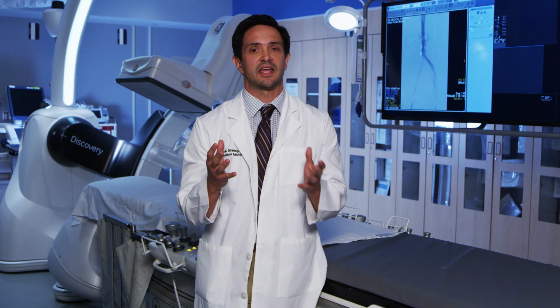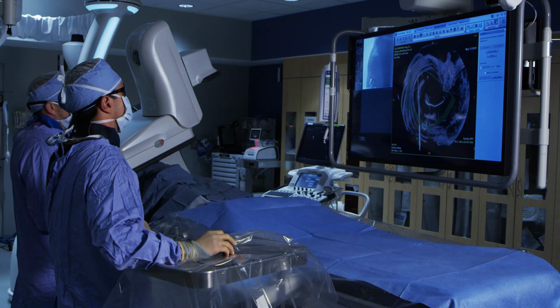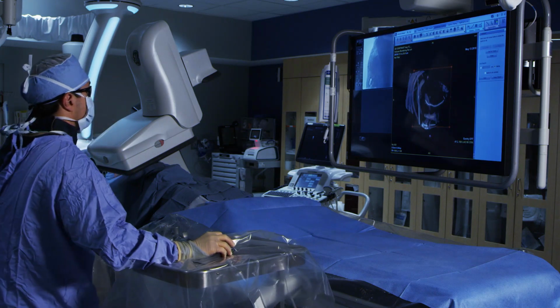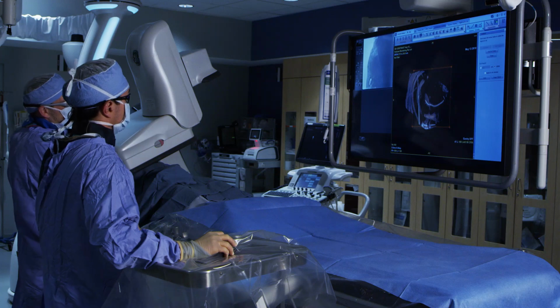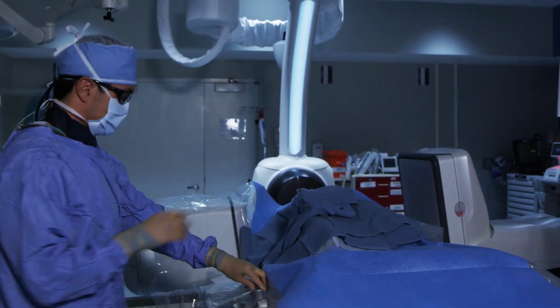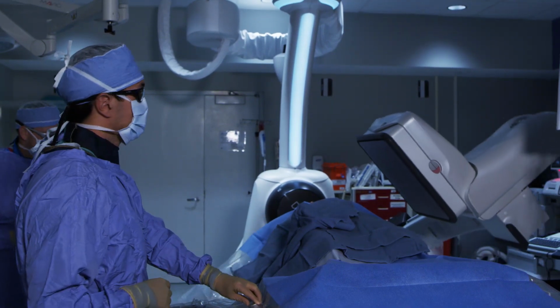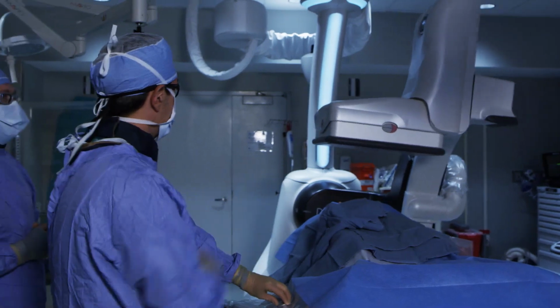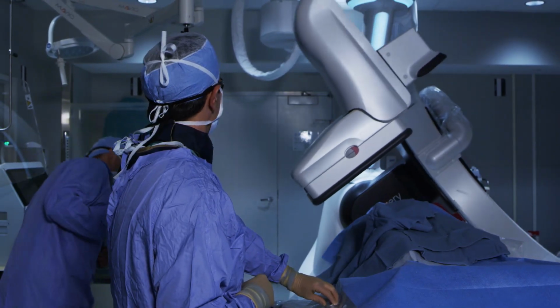With this rotational 3D CT software and the trajectory planning, I can get my needle at any complex angle, which essentially has allowed me to treat a much higher number of patients that I previously would have not been able to offer treatments to. Most cone beam systems that I've used have needle assist type software. The problem with a lot of those systems is that there's not enough room under the gantry once I've acquired the image and have applied the 3D overlay to actually get under the gantry to then place the needle comfortably. With this system, because the gantry is so much larger and there's so much more room underneath it, I found that there's almost never a situation where I'm limited in using the needle assist software just by virtue of being able to get under the equipment.